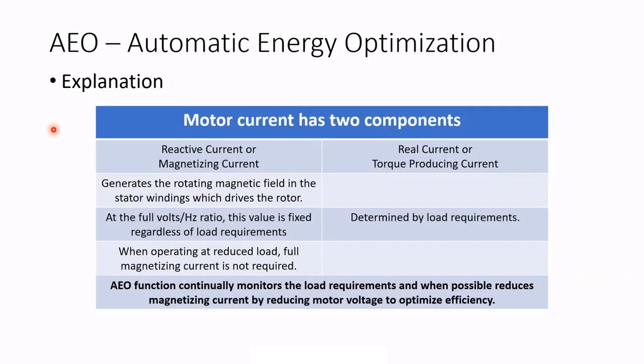AEO — the automatic energy optimization. Let's understand first that motor current has two components: the reactive current, also called the magnetizing current, and the real current, also called the torque-producing current. The magnetizing current generates the rotating magnetic field in the stator windings which drives the rotor — basically makes a big spinning magnet. At the full volts-to-hertz ratio, that magnetizing current is fixed, regardless of the load.